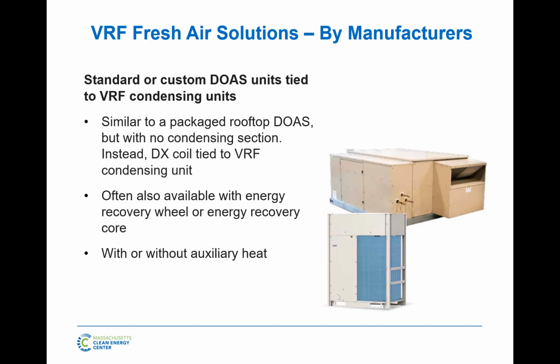Or like I mentioned, a lot of VRF manufacturers now build their own. Some VRF manufacturers have built these with VRF inverter compressors in them, with VRF condenser fans in them. That's one way. Some VRF manufacturers have done this. So here's a rooftop, but there's no condenser section in it. You just use our condensing unit and connect it. So that happens too.